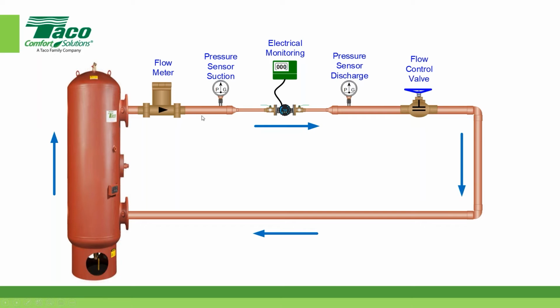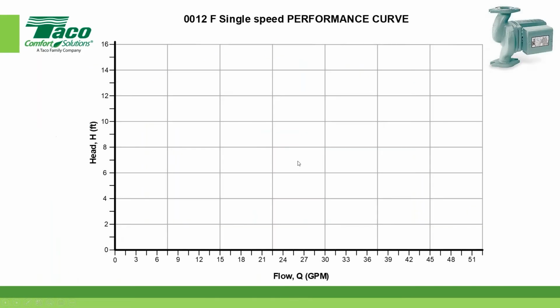Mind you, all of the air is out of everything in this system. I've got a little air vent up here. Everything's gone. It's nothing but fluid inside there. I'm going to close this. I'm going to turn it on, okay? And then I'm going to look at the pressure transducers, on the outlet side, and I'm going to see at no flow. Remember, that's how this reads.